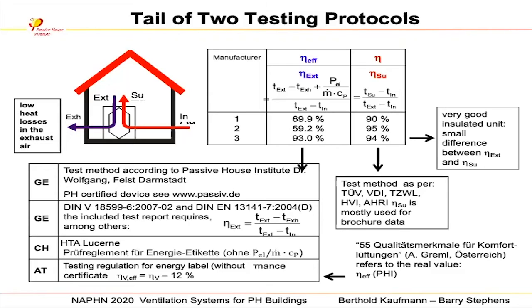In a nutshell, shown on this slide, the red arrow in that house shows how AHRI and HVI in North America test efficiency. They test the incoming airstream, and they determine what the incoming temperature is from outside and what it's delivered inside versus the leaving air temperature, and the percentage of what they call recovered energy. The problem is that the incoming airstream has a lot of influences. It's got motors in there that produce waste heat. You've got cross-flow contamination. You've got what they call casing leakage, which Berthold mentioned earlier, where if the box is not well insulated, then you're going to have an influence on that airstream as well. As a result, the efficiency number you get for the incoming air is not a great number for putting into an energy model.